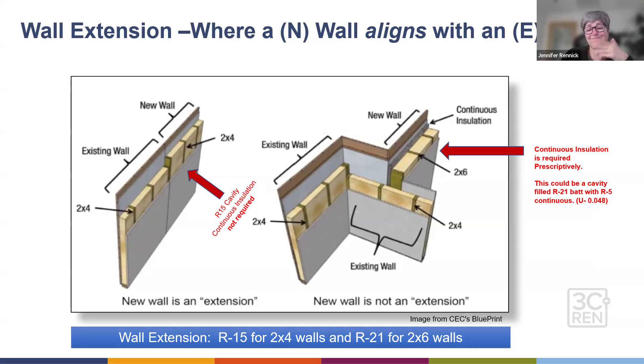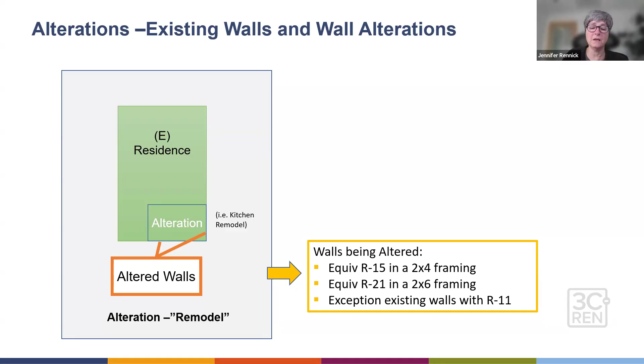Same idea for alterations now, which is a change from last time. If you alter a wall, like in your kitchen remodel, and where that wall gets altered or changed, if all the insulation is taken out to add new windows, for example, then you put R15 in a 2x4 and R21 in a 2x6. And if those existing walls already have R11 insulation in them and you're not touching them, you could just leave them.